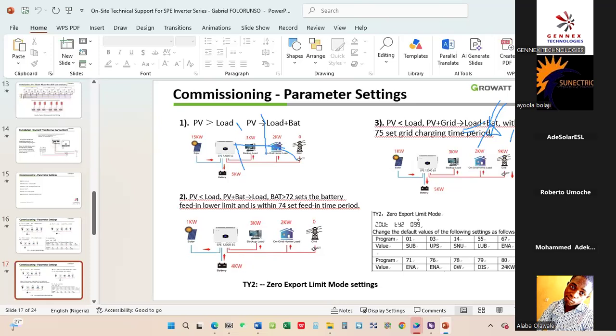So that is what we call the zero export limit mode. If you look at this diagram now, there is a CT here. Do you see that CT? This CT is somewhere there, used to checkmate whether current is either flowing to the grid as you're feeding in, or you are not feeding it. It's all about the programming.